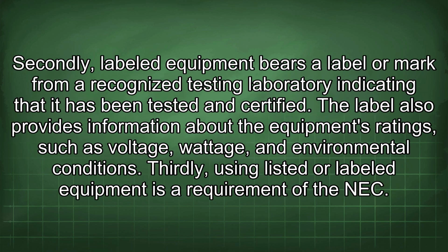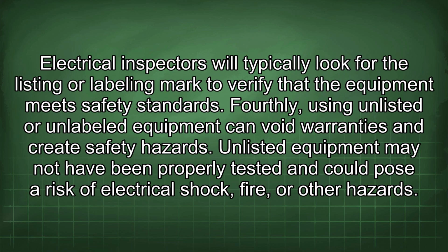Secondly, labeled equipment bears a label or mark from a recognized testing laboratory indicating that it has been tested and certified. The label also provides information about the equipment's ratings, such as voltage, wattage, and environmental conditions. Thirdly, using listed or labeled equipment is a requirement of the NEC. Electrical inspectors will typically look for the listing or labeling mark to verify that the equipment meets safety standards. Fourthly, using unlisted or unlabeled equipment can void warranties and create safety hazards. Unlisted equipment may not have been properly tested and could pose a risk of electrical shock, fire, or other hazards.